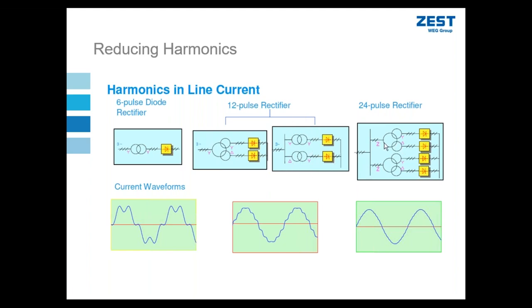And this just shows a 24 pulse configuration in its simplest form. I need 4 secondary windings. We have some flexibility. We can change this. We can put multiples of 4. I can also do 1 single primary and 4 secondaries on 1 transformer, or I can split it into 2 transformers as shown.